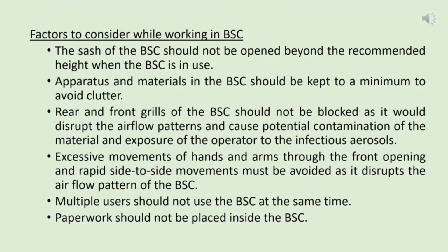And you also need to understand there are factors to consider while you're working in a biosafety cabinet. As I mentioned earlier, the sash of the BSC should only be open to the appropriate height. If you open it all the way up and put your whole upper body in, then you won't be protected from infectious aerosols, etc.